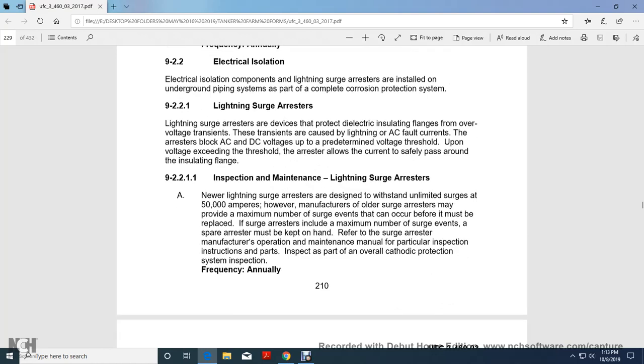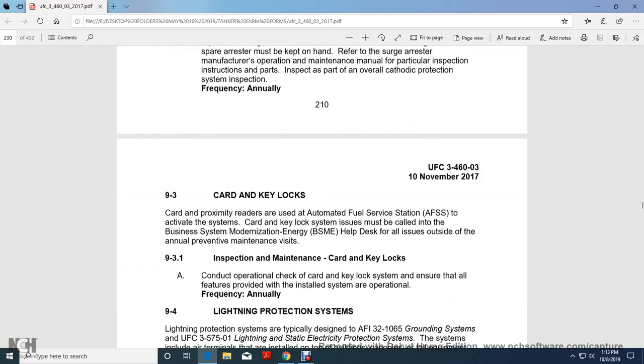Inspection and maintenance of lightning surge arresters. New lightning surge arresters are designed to withstand unlimited surges of up to 50,000 amperes. However, the manufacturer of older surge arresters may specify a maximum number of surge events, after which the arrester must be replaced. Remember, a spare arrester must be kept on hand. Refer to the surge arrester manufacturer's operation and maintenance manual for particular inspection instructions. Inspect this part of the overall cathodic protection system annually.